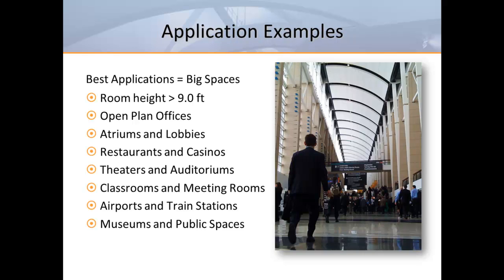When thinking of displacement ventilation, big spaces are absolutely the best applications. Any spaces with room heights greater than 9 feet and enough open floor space to allow the proper air pattern to develop should be ideal. If the space will be occupied by moving people, like visitors to a museum or travelers walking to a departure gate, that's also ideal because the adjacent zone shouldn't be an issue.